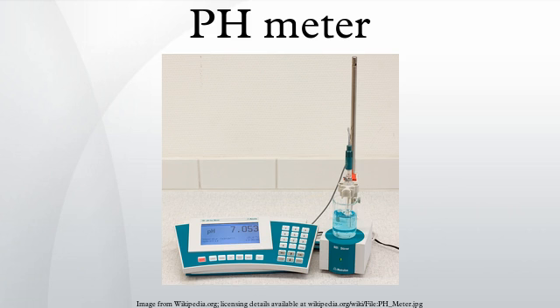Never touch the bulb by hand and clean it with the help of an absorbent tissue paper with very soft hands, being careful not to rub the tissue against the glass bulb in order to avoid creating static. To measure the pH of a solution, the probe is dipped into the solution. The probe is fitted in an arm known as the probe arm.